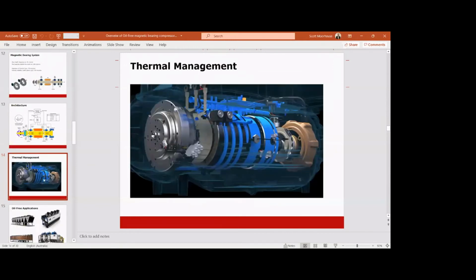So these compressors are very compact, and having an inverter on board the compressor, we need to cool a lot of the electronics, and we need to cool the IGBT, and we also need to cool the motor. So the thermal management on these compressors can become quite complex, but it is one of the keys to being so small. The compressors are extremely small.